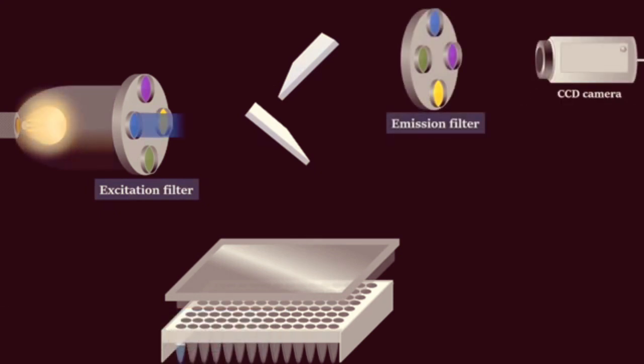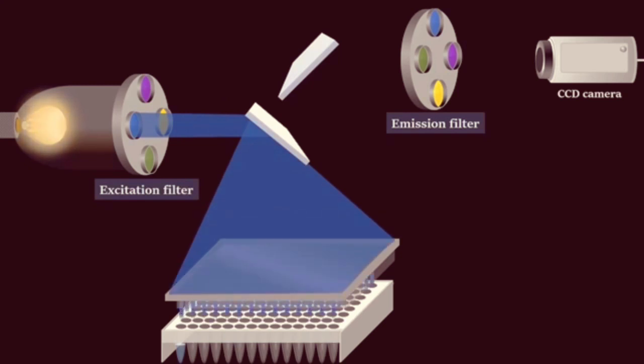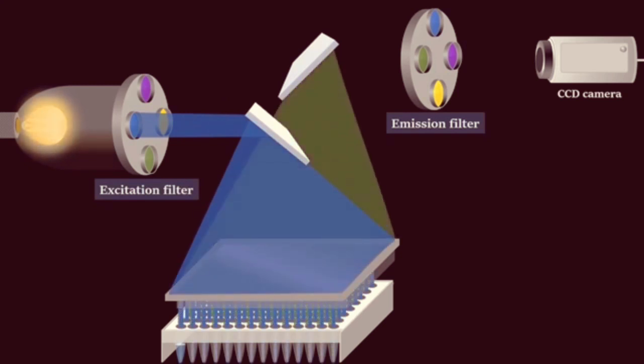Filtered light from the lamp is reflected off mirror, passes through a condensing lens, and is focused into the center of each well. Then fluorescent light emitted from the wells reflects off the mirror, passes through an emission filter, and is detected by the CCD camera.